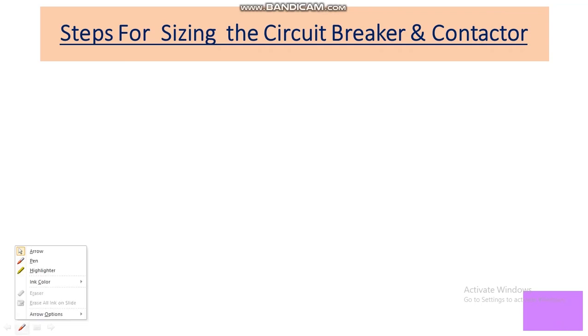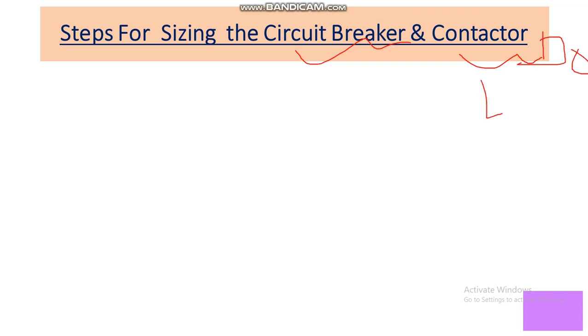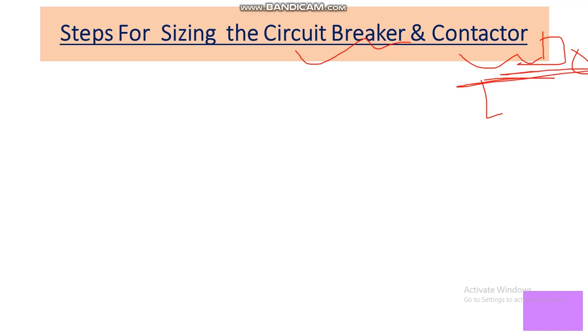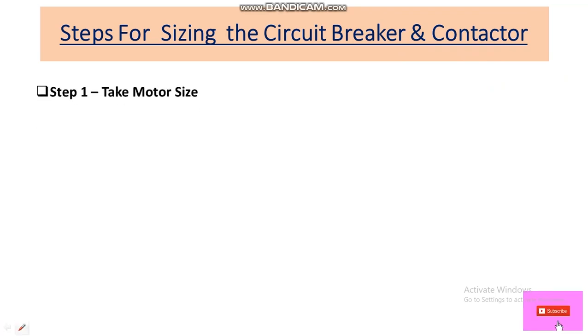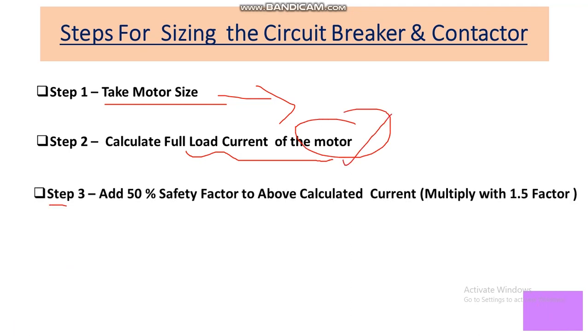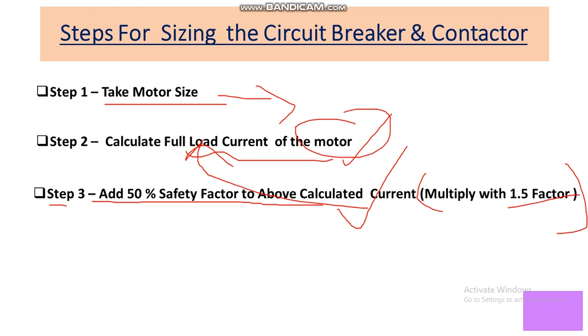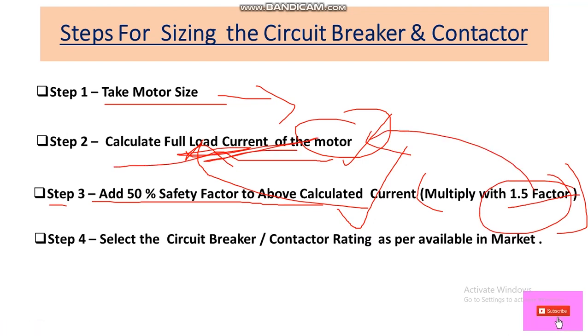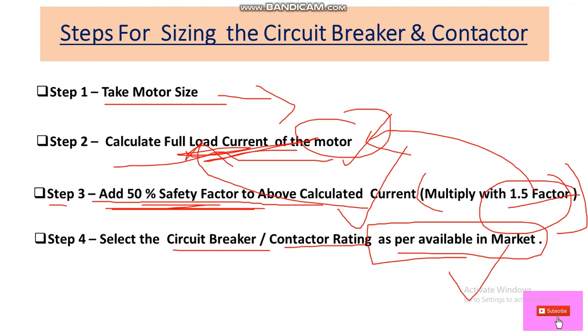We have some steps for sizing the circuit breaker and contactor for the starter. I am talking about DOL starter — not a star-delta starter; we will discuss star-delta contactor selection later. So this is only for DOL starter. In step 1, we take the motor size. In step 2, we calculate the full load current of the motor as per motor capacity. In step 3, we add a 50% safety factor to the full load current, or multiply by 1.5. Finally, we select the circuit breaker and contactor rating as per what is available in the market.